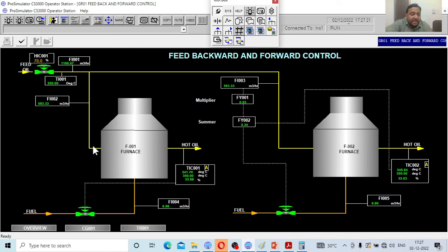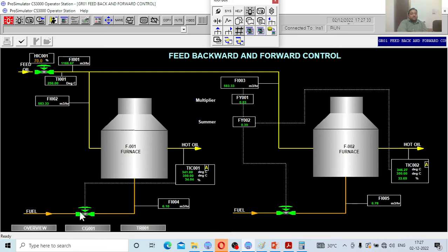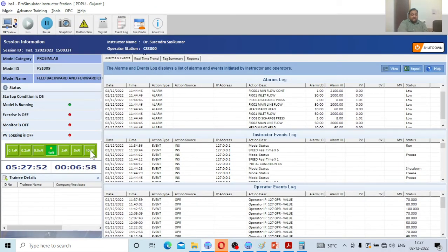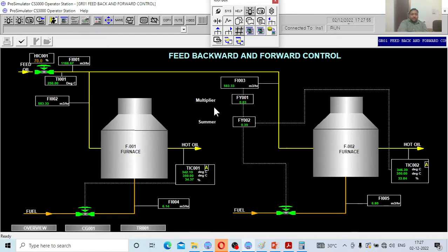On the feedback side, there is no sensing element as such — the process will first disturb the furnace parameters, then the exit temperature of the oil will change, and then the controller will take action through the valve. Now you can see: 341 and 350 on the left — the set temperature is 350 and the process value is 341. On the right, the set temperature is 350 and the present process value is 349, meaning it has reacted more quickly and instantaneously.